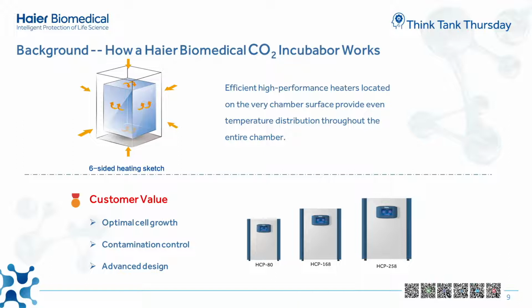However, filling and heating the incubator can take time, so a water jacket incubator comes with a longer startup process. Once the chamber walls are filled with water, the incubator can become very heavy and difficult to move. Considering stagnant warm water is an ideal place for contamination growth, another downside of the water jacket incubator is that algae and bacterial growth can easily take place within the chamber. So air jacket incubators are much lighter, faster to set up, and provide similar temperature uniformity as the water jacket one.